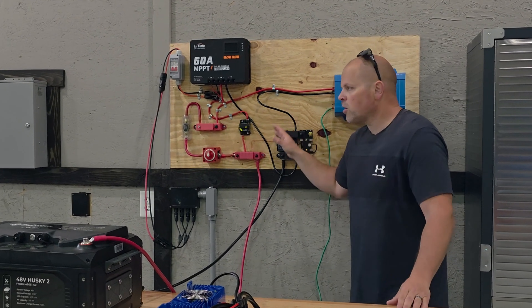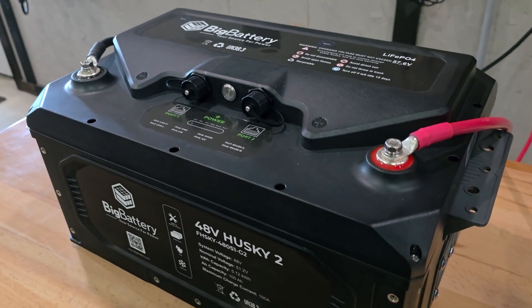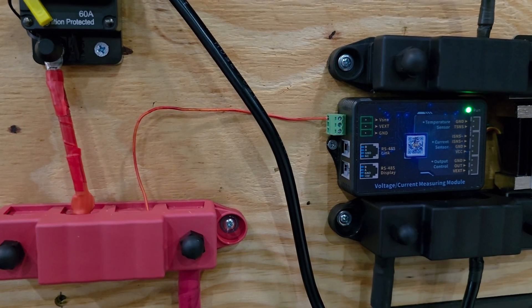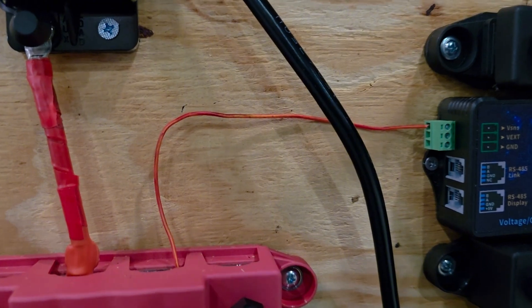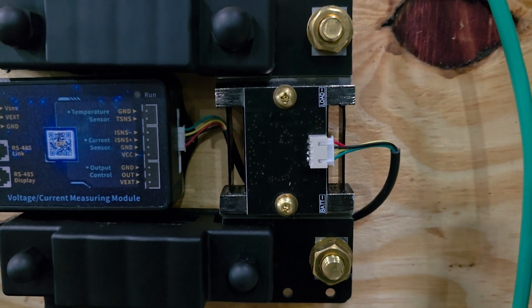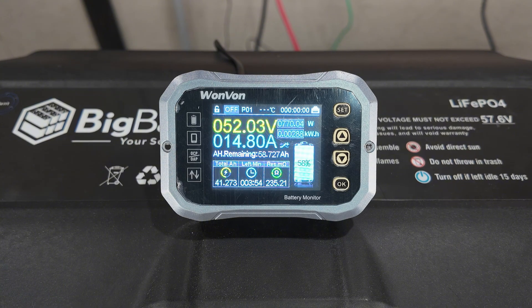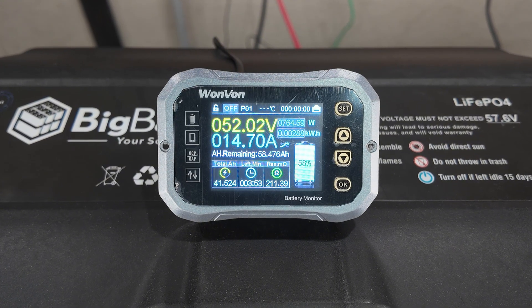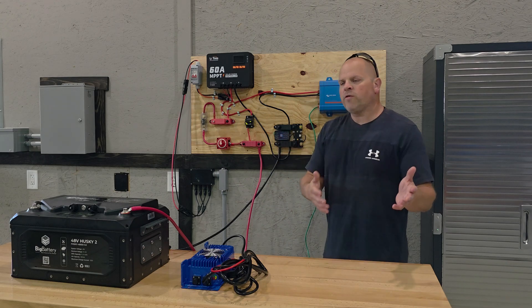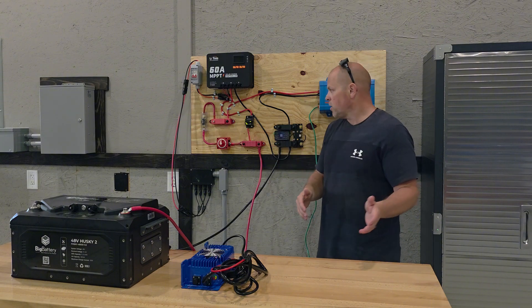Currently, I have the system turned off other than the shunt. The shunt is connected to the positive and the negative cables of the battery. We have a small wire coming here for the power line coming into the shunt, and then we have that connected into this positive bar. So that allows me, in discharge, to monitor the amount of consumption or the amp hours that we're using out of the battery. I wanted to explain that because I don't want you focusing on the light thinking the system is turned on — it's just that the shunt meter is turned on.